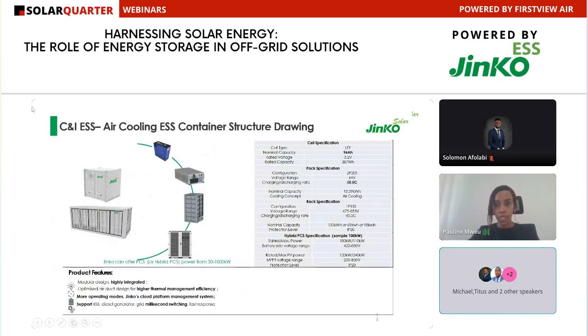These are the cell specifications, the specifications of the cells, the packs, the rack, and the hybrid PCS - this is just a sample. For the cell specification, it's a 96AH, 3.2 volt system. For the hybrid PCS, the specification in this case is that it's a 100 kilowatt rated PCS, and the maximum power it can produce is 110 kilowatt.